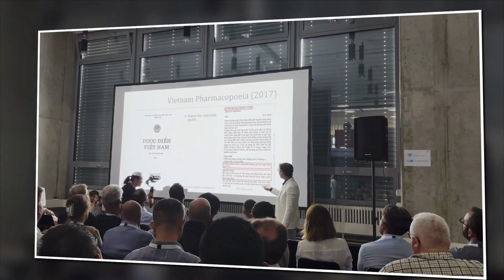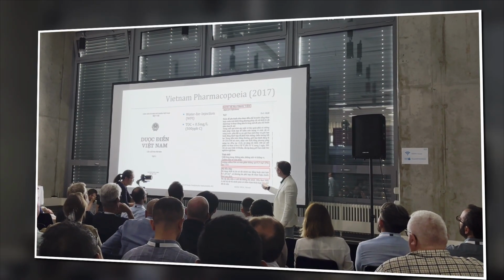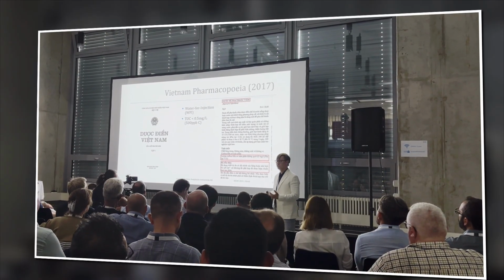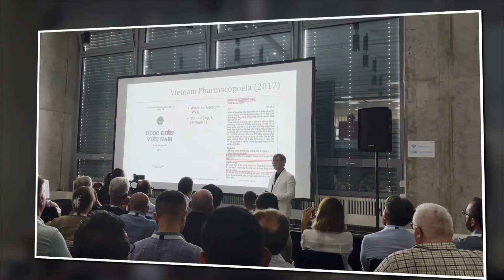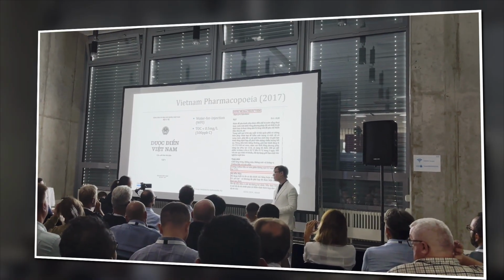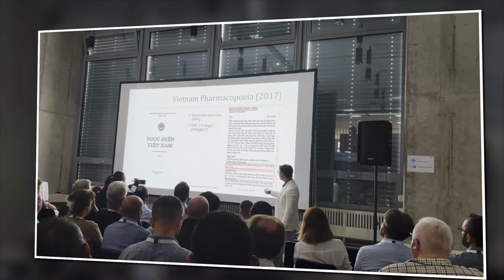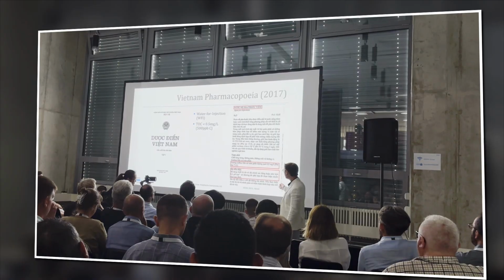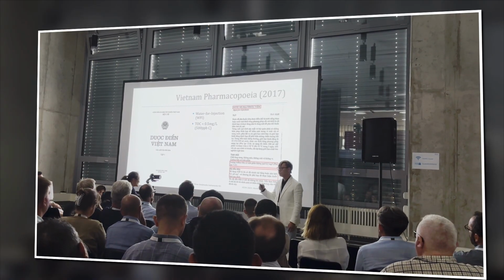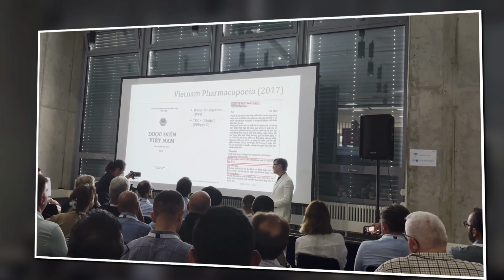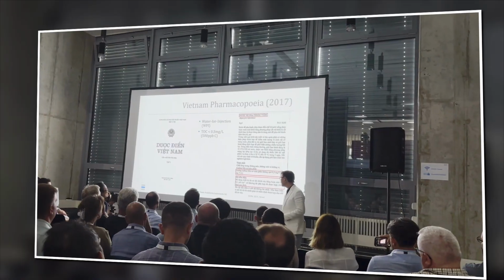The USP or the EP regulation says TOC concentration should be less than 500 ppb carbon. And in the Vietnamese pharmacopoeia, the TOC concentration should not be above 0.5 milligram per liter, similar to 500 ppb. Yes, this is by law.